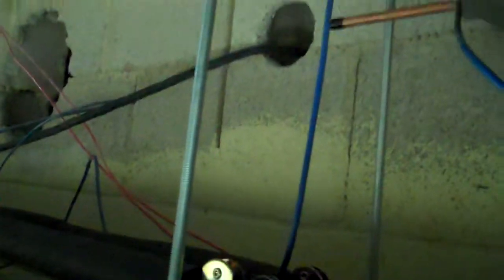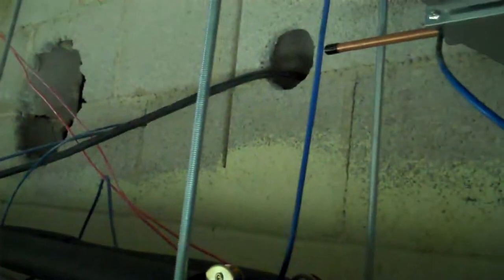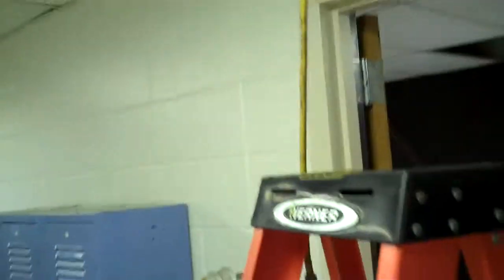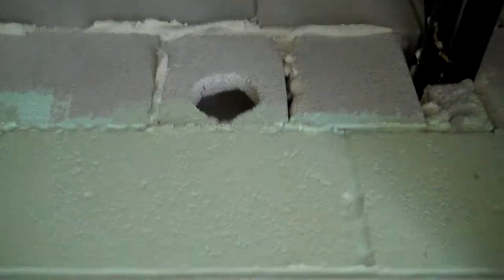And you only have a 2-inch hole that goes through the wall, or a 3-inch hole? Yes, we have a 2-inch hole that goes through the wall for the refrigerant line sets, and then we have an 8-inch hole that goes through the wall for exhaust and fresh air. Let's take a look inside and see where those go. These refrigerant lines, will they be going through here as well? They're going to, there's another room behind us. Oh, there's a room behind us. Computer lab behind us. There's a computer lab, so this works for computer labs too.